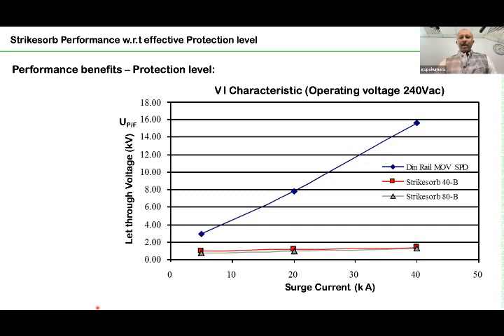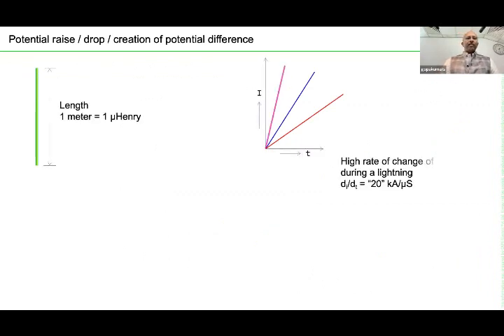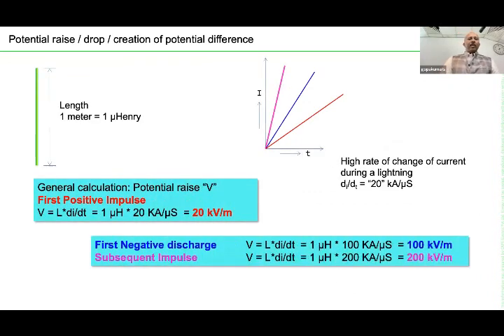I am sure you are aware of the problems with respect to lightning current flow in a conductor. Once the lightning current flows through any conductor, depending upon L di by dt, that is its length and the rate of change of current, a large voltage is accumulated, or there is a large potential drop on this particular conductor, based on which separation distances and many calculations and recommendations are made in the standard.